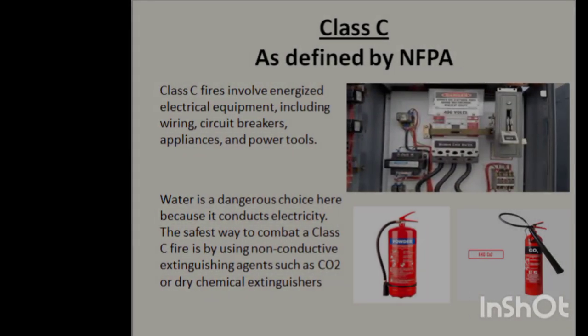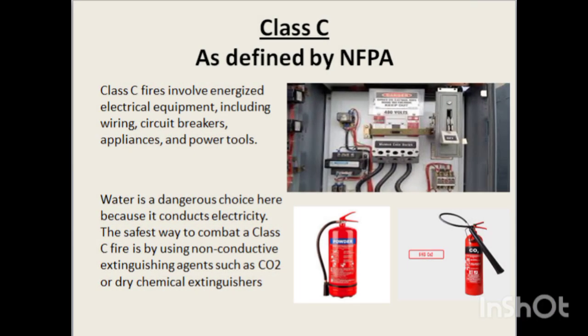Class C fires involve energized electrical equipment, including wiring, circuit breakers, appliances, and power tools. Water is a dangerous choice here because it conducts electricity. The safest way to combat a Class C fire is by using non-conductive extinguishing agents, such as CO2 or dry chemical extinguishers.